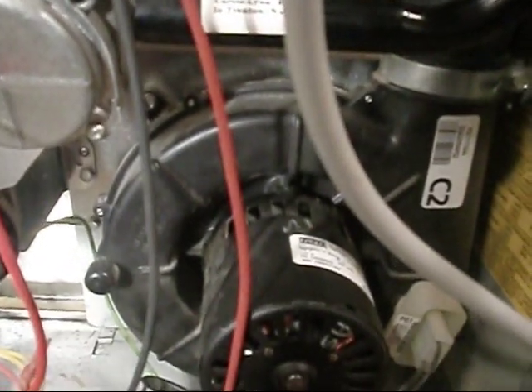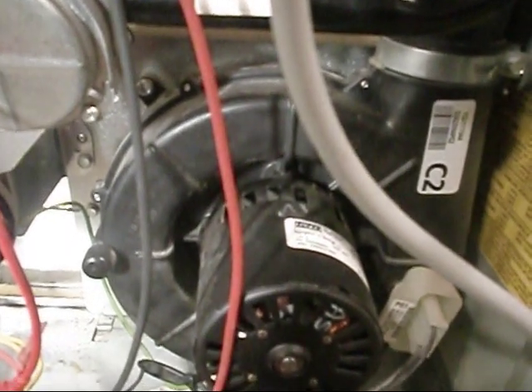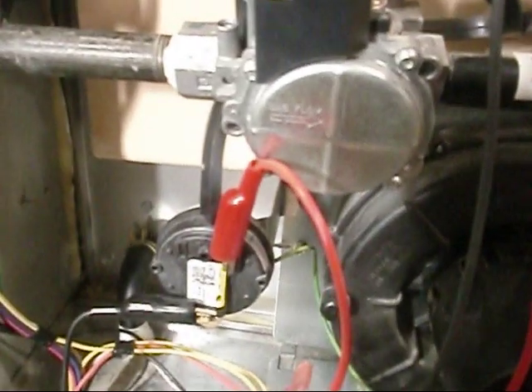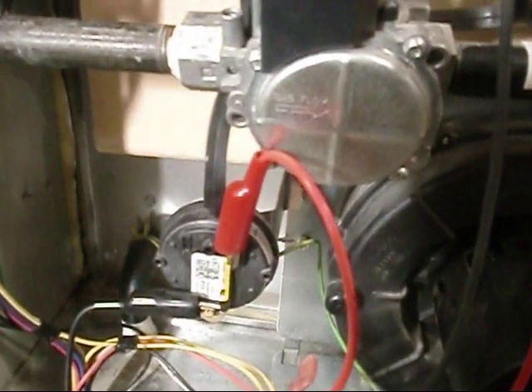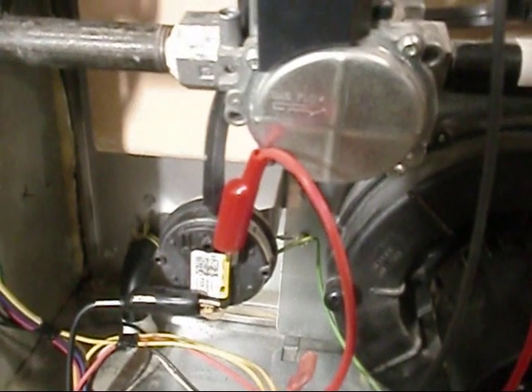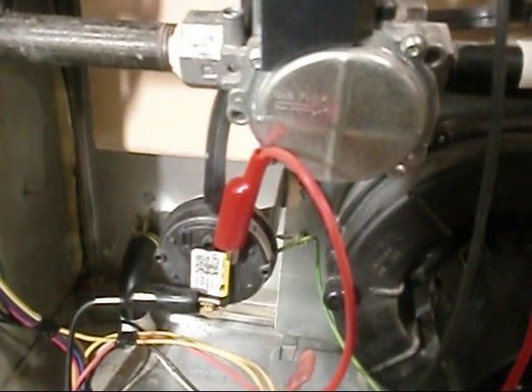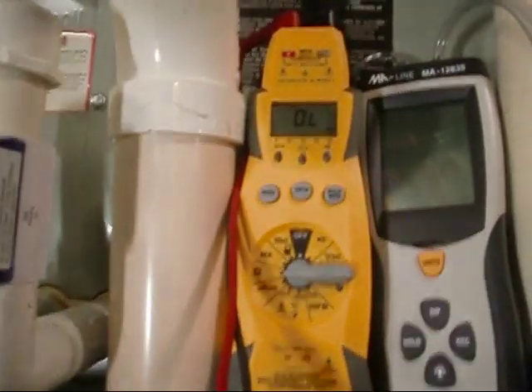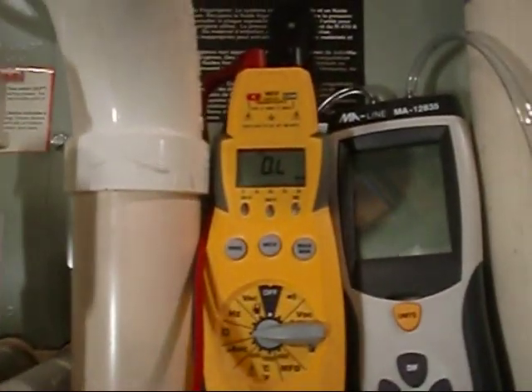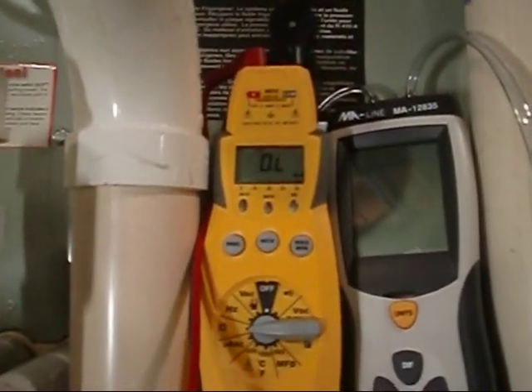And what we're actually going to do here, y'all, is we're going to do an ohms test. So we'll actually pull her on down over to ohms, and if you see right there, it's showing open line, which that switch hasn't made yet. So what we're going to do here is when I hit that electric over there, we should have some resistance.